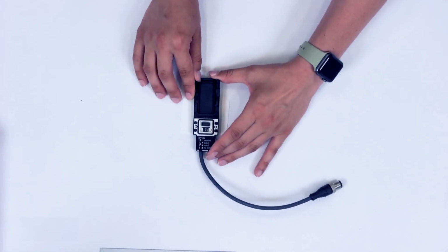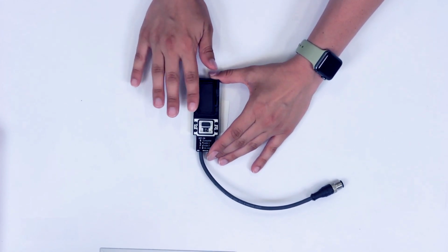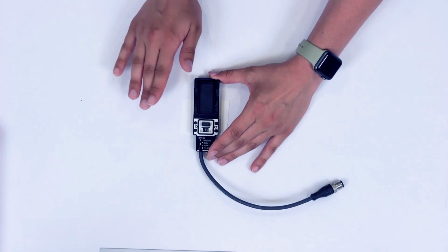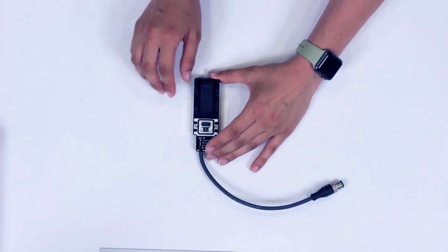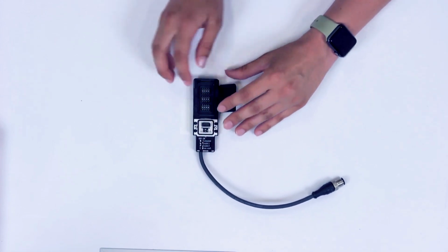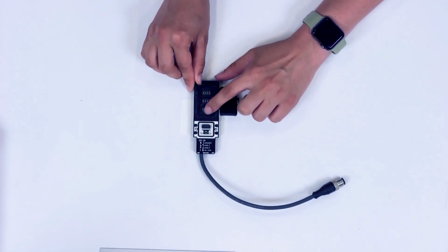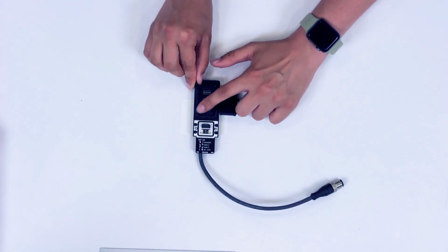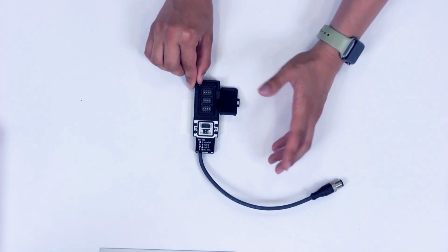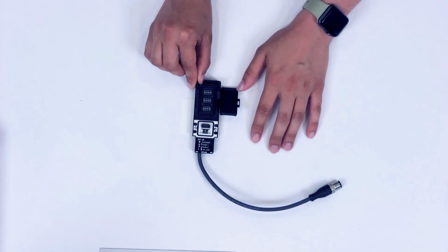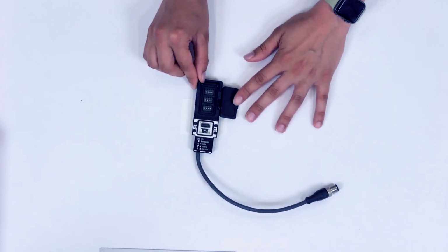Here I have our system plug 2. This is the system plug that will go on the receiver side of the light curtain because that's where the intelligent processing occurs. If I remove this cap here, you'll be able to see our dip switches. Within this feature set, we'll be programming the dip switches in rows B and C. So that's the bottom 2 rows. Once you figure out the width you're looking to safeguard, you can then set your dip switches according to our dip switch configurator in the SICK Safety Assistant app.